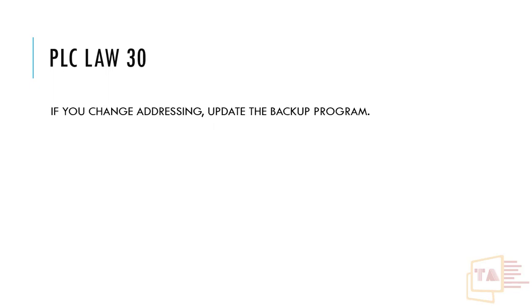If you change I/O addressing, update the backup program. If you have an input terminal and there are spare I/Os, and one gets damaged, you move the connection to a spare — then you must update the program addressing accordingly. Back up the program, change the address name, and change the command for that input so the backup stays current and useful.